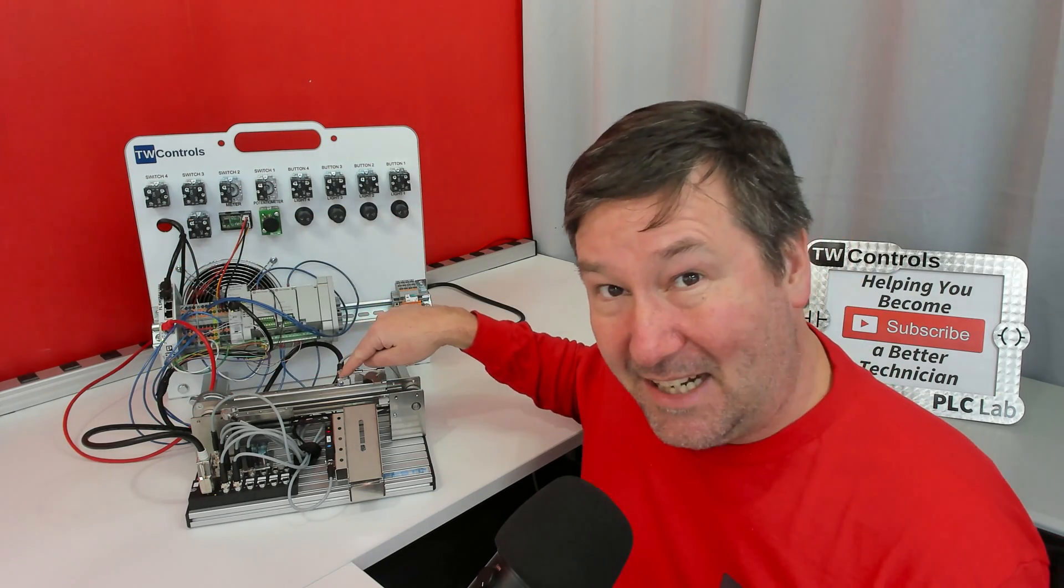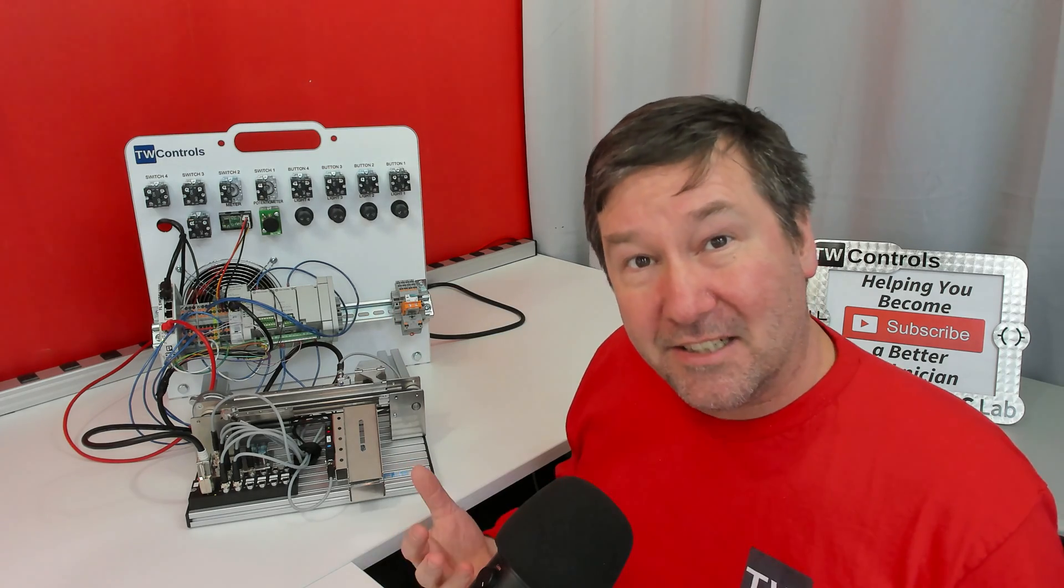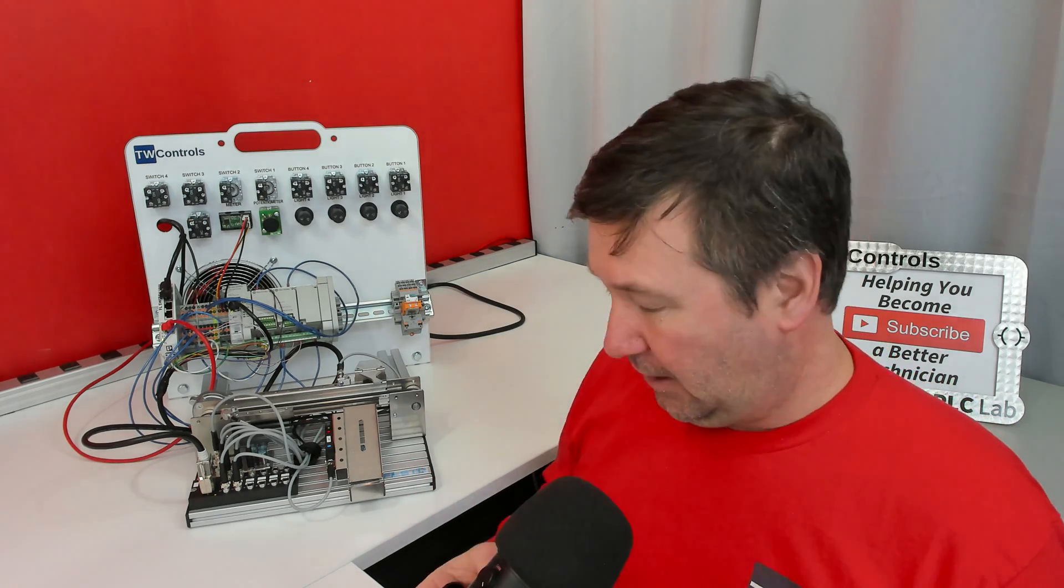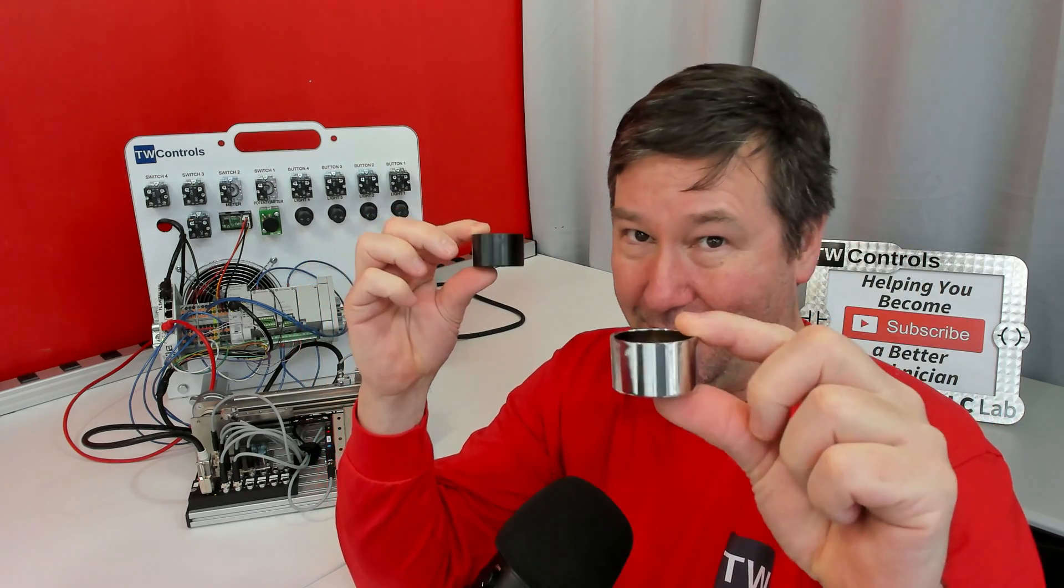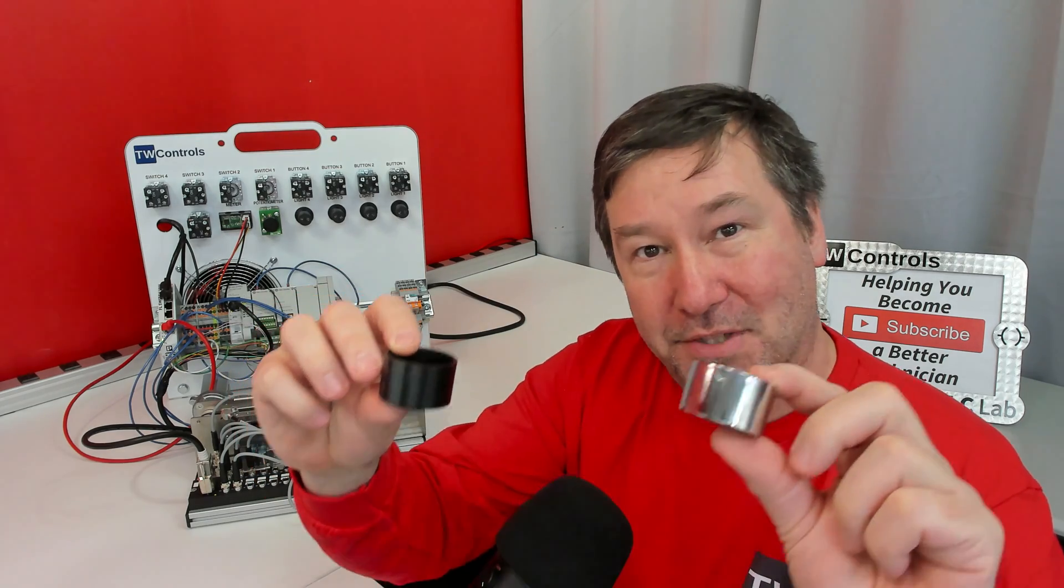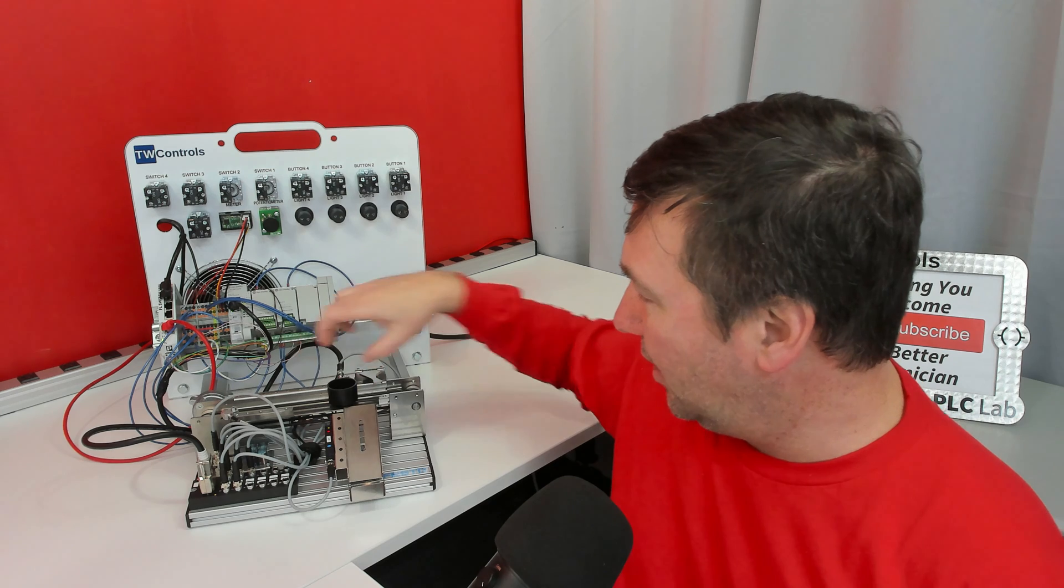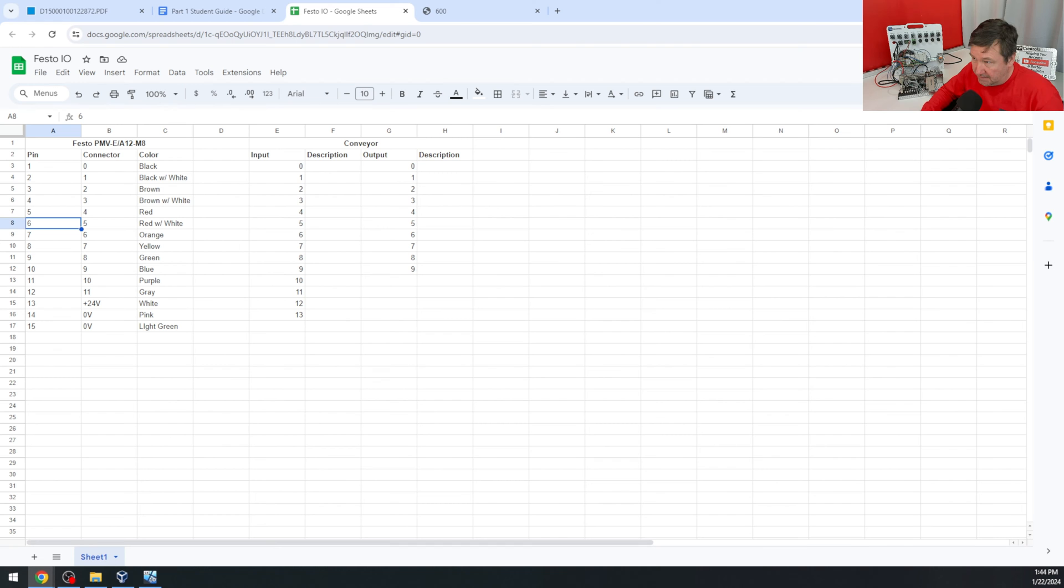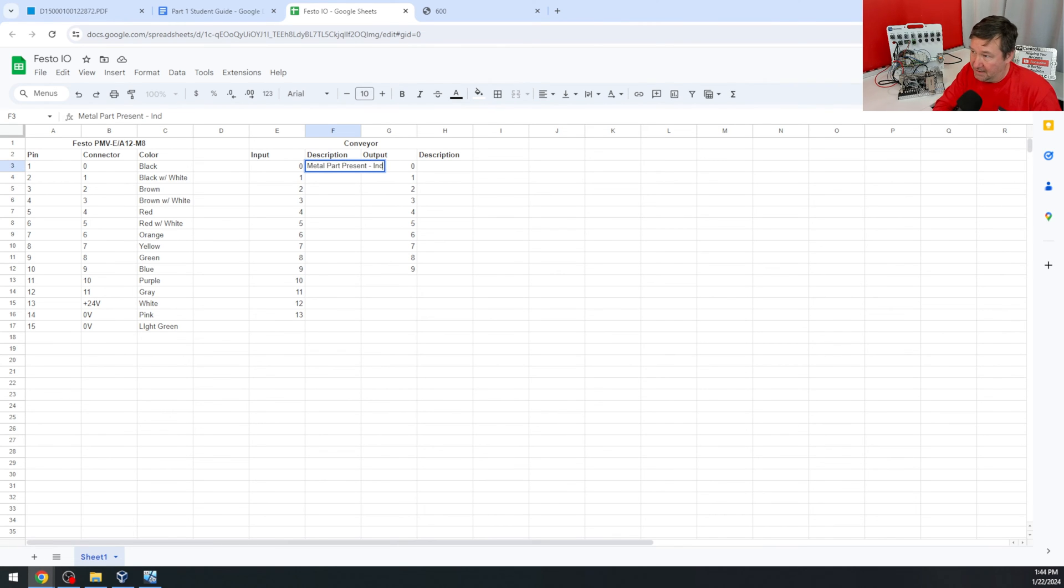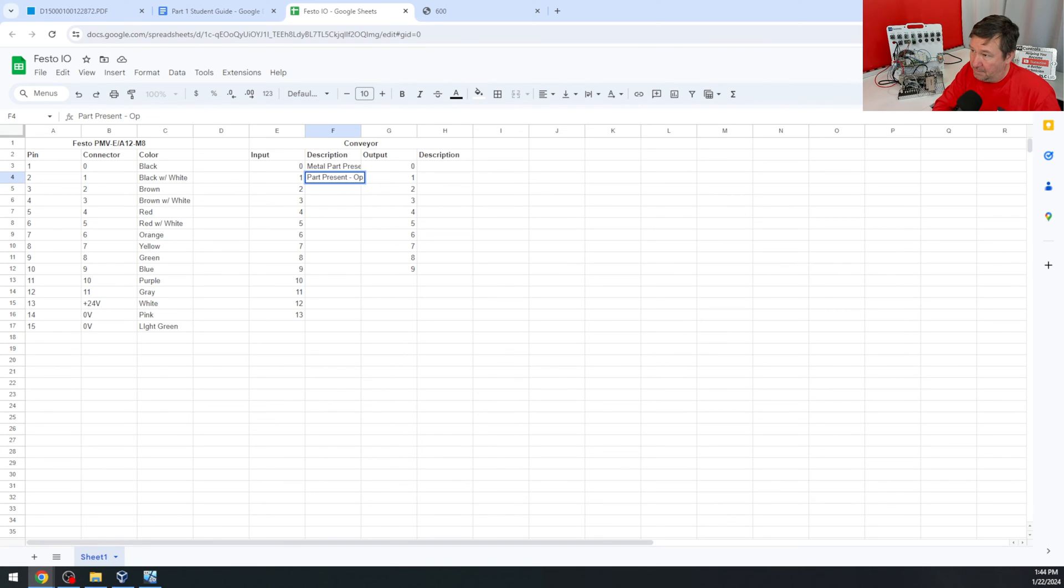This is an inductive sensor. And what that means is it's looking for things that current can flow through. And so this conveyor comes with shiny parts, which are metallic, and black parts, which are plastic. If I stick the black part in front of it, then it's not going to sense anything. But if I place the metallic part in front of it, then it's going to sense it. So let's start working out some descriptions for IO. Input zero is going to be metal part present. And I'm just going to put inductive. And then one is going to be part present. And it's optical.